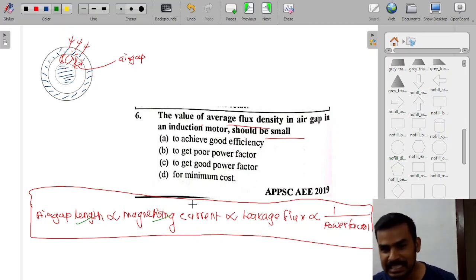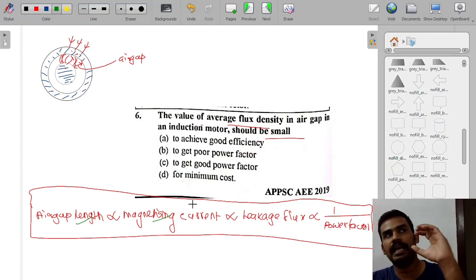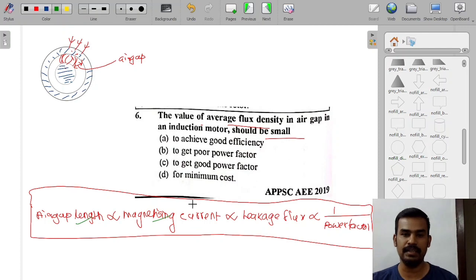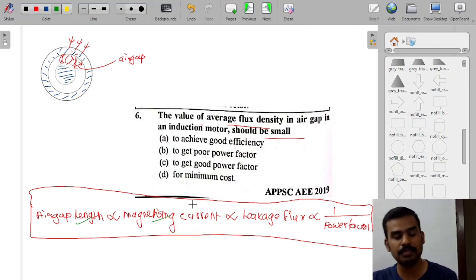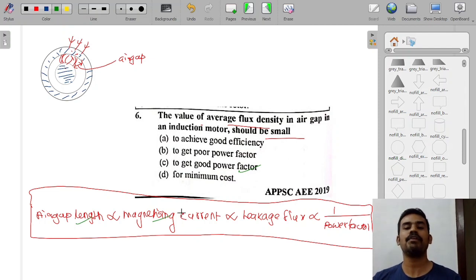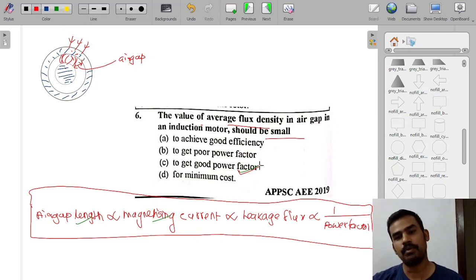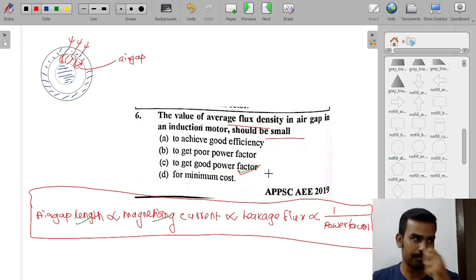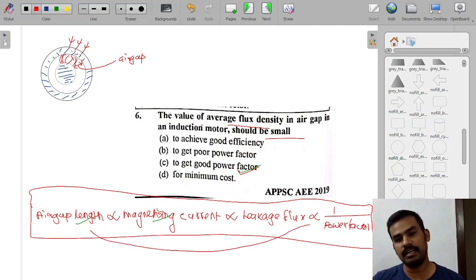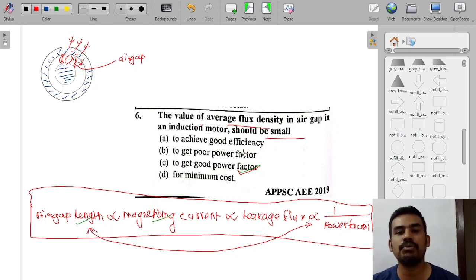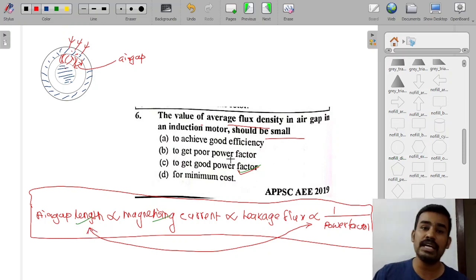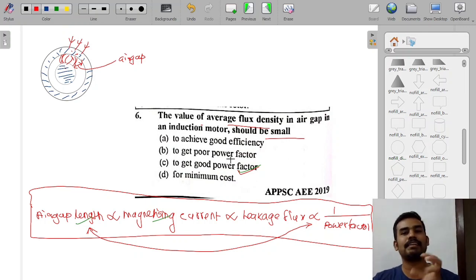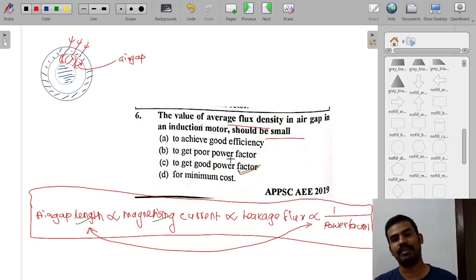The air gap in an induction motor should be small. The reason is: to get a good power factor. The power factor is the primary thing — a small air gap reduces the magnetizing current and leakage flux, thereby improving the power factor and efficiency of the motor.